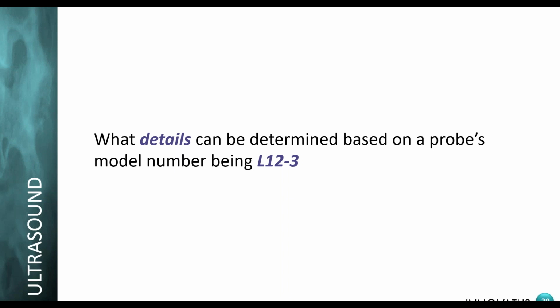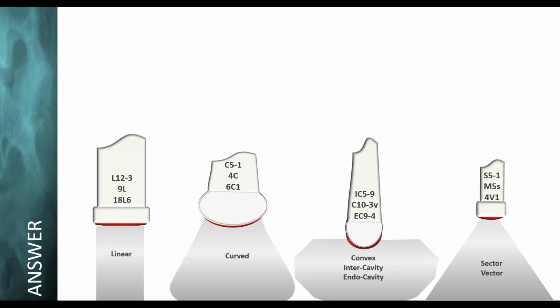Because where you're going with that is the older Philips probes, the size of the aperture used to be in the designation. Philips used to have a probe that it was an L12-5, 38 millimeter or 50 millimeter. So they did put the size of the aperture or the footprint within the probe designation. This L12-3, what it tells you is it is a linear. And so we have this type of image formation. The 12-3 gives you the frequency range of this transducer. And so this transducer can go from 12 megahertz to 3 megahertz.